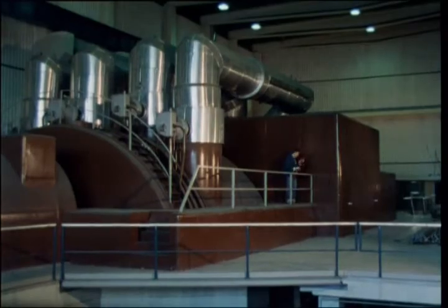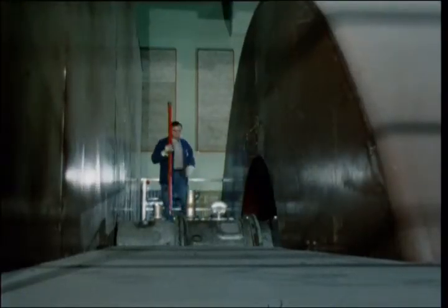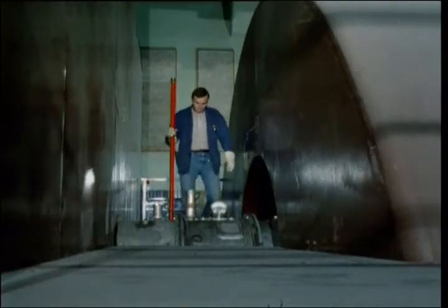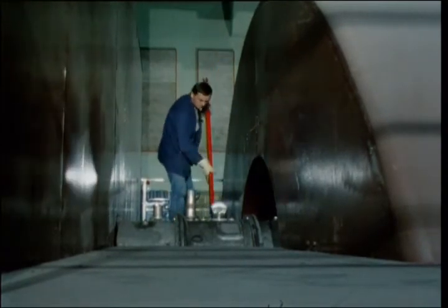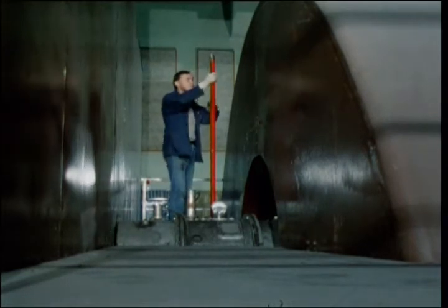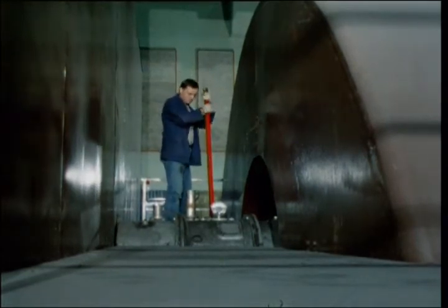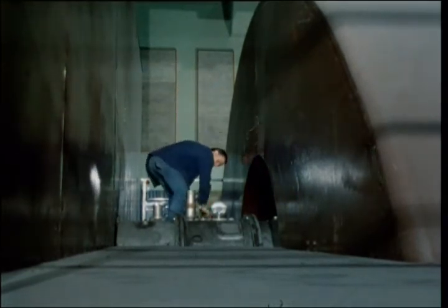Each day, too, the turbine was rotated manually to circulate inhibited lubricant to the moving parts. With the changes in the fuel price, after about 3 years, the plant was put back into service without any serious corrosion problems.